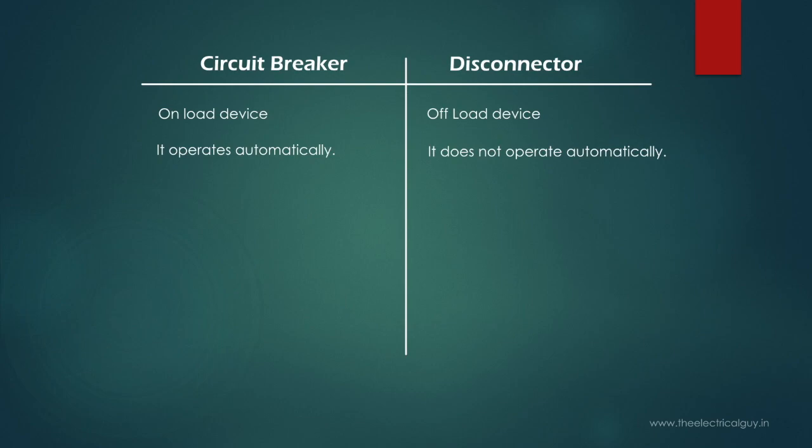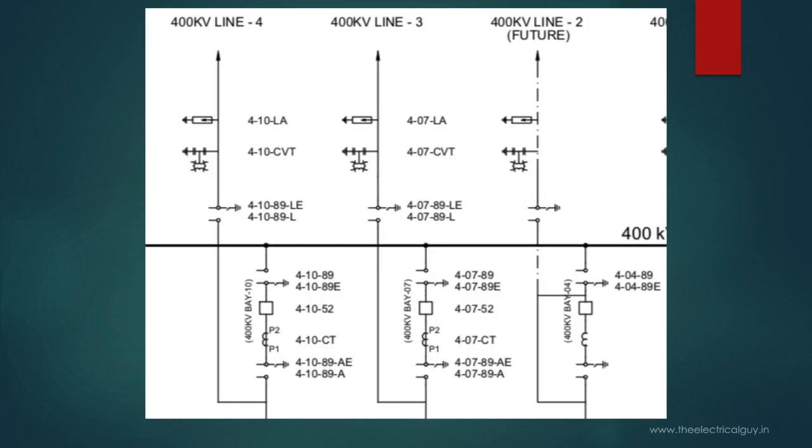As the name suggests, disconnector or isolator is used to disconnect or isolate part of a system which needs to undergo maintenance work. To understand this we will have a look at a single line diagram. So as you can see this is an SLD of a 400kV by 245kV substation. This symbol indicates the horizontal center break type disconnector with single earth switch and this symbol indicates the circuit breaker.